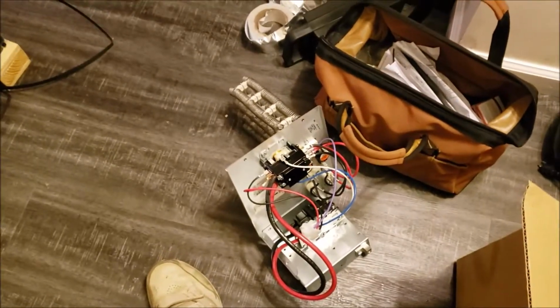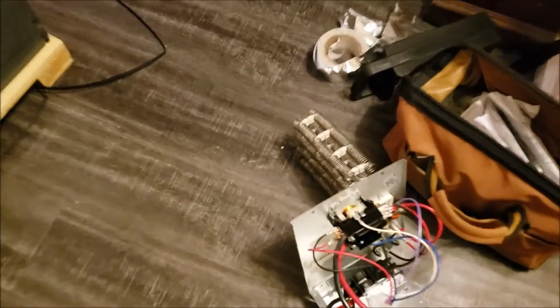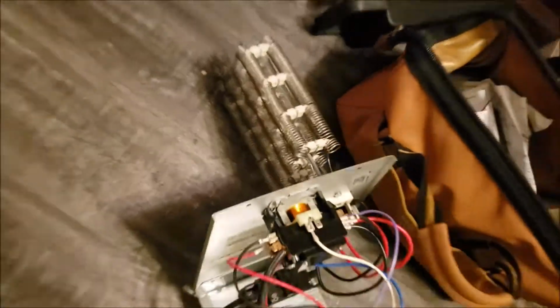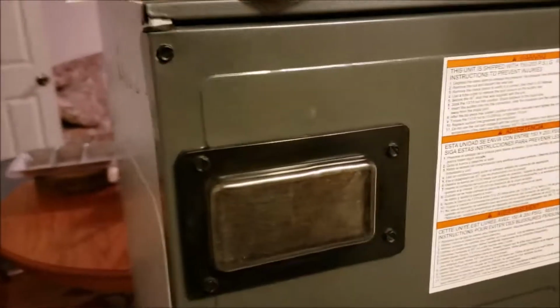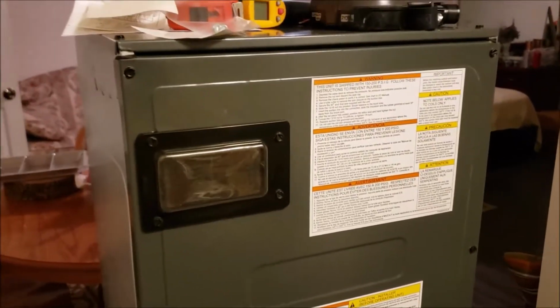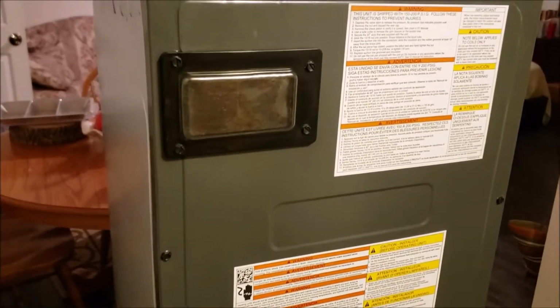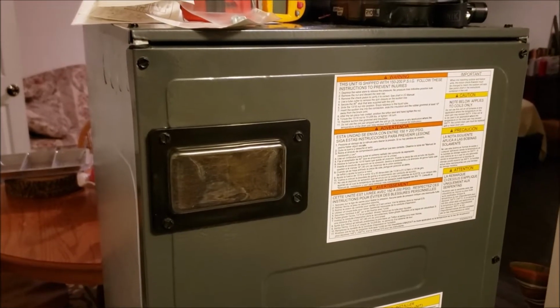But before I do anything, we've got to put in the heat strips, 10 kW heat strips. It's amazing those little coils can heat your whole house. If you look down in here, there are no heating coils at all — it doesn't come with one. So keep that in mind if you order one of these: you also need to get your heat strips, or you won't have any supplemental or backup heat for the heat pump. When you get below 30 degrees, the heat pump alone is usually not enough to keep your house warm in more northern climates.